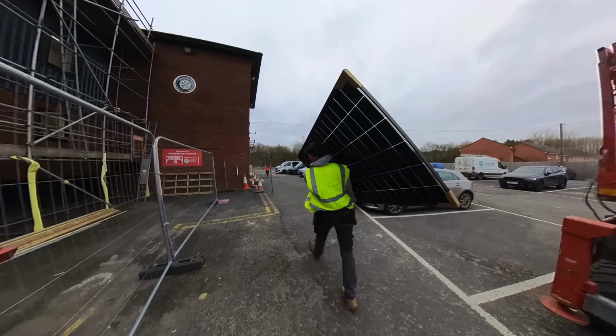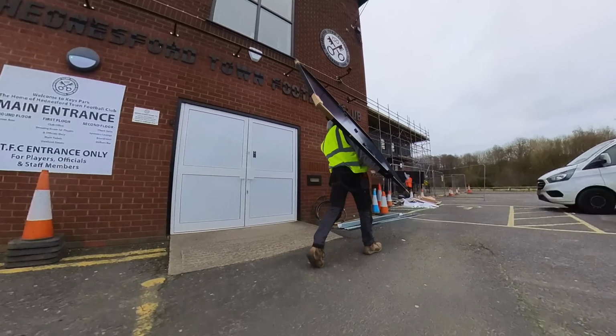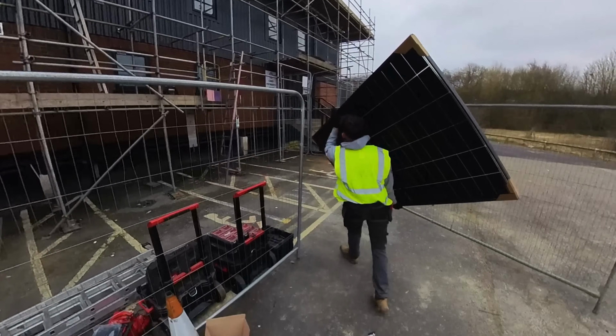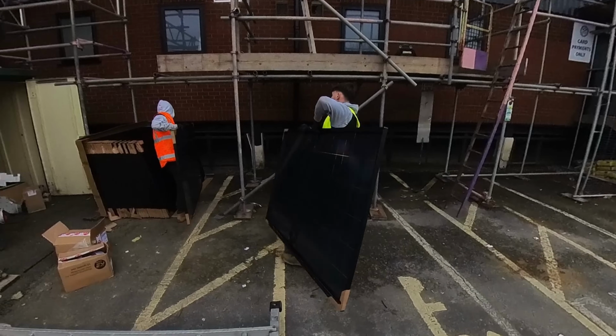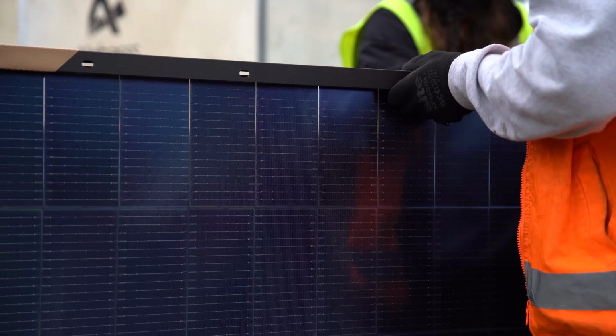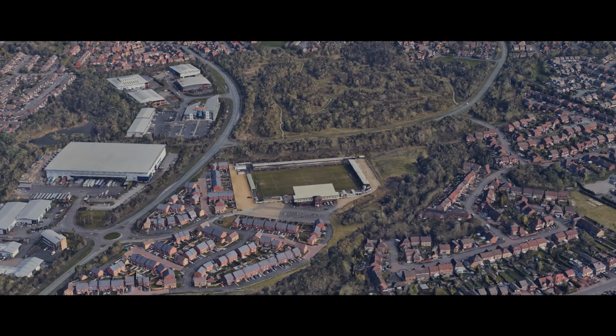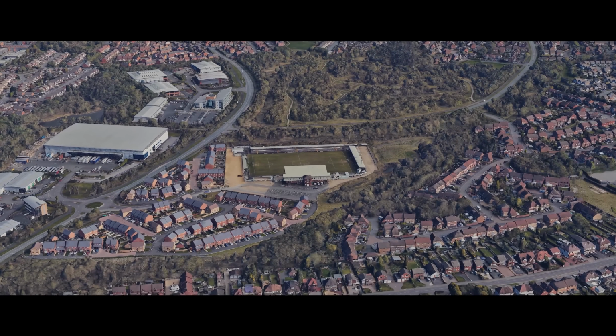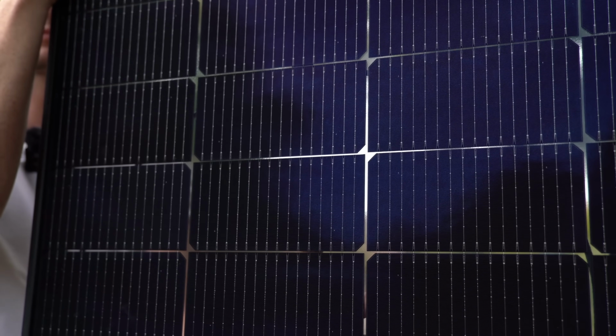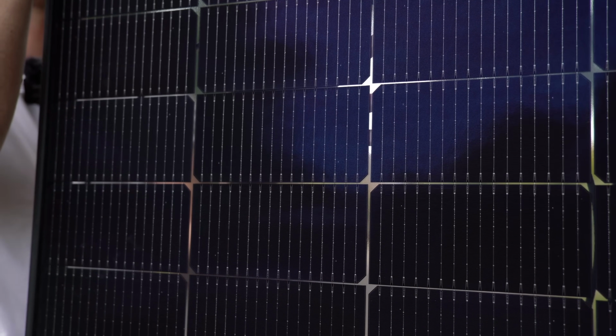So let's talk about the choice of panels that we're using here. Now these are the standard REA Fusion 2s that we use on all of our domestic projects. They're a 450 watt bifacial HJT panel. Now these are super high performance and very premium, but they were actually specifically requested by this client who is a subscriber to this Heatable YouTube channel. So we're installing 227 of these, which totals about 102 kilowatts, and we're expecting great things on this light grey roof, because as you can see here, between all the cells on the panels, we've got this clear back sheet that allows light through, powers that back side of the panel, and gives you even more power.